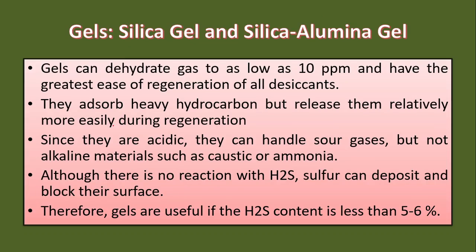These gels can dehydrate the gas to as low as 10 ppm and have the greatest ease of regeneration of all the adsorbents. That is a very good thing, because regeneration requires low heat as compared to simple alumina. They adsorb the heavy hydrocarbons but release them relatively more easily during the regeneration process. So that is one of the very important things. Although they adsorb, they have a very low heat requirement for regeneration.